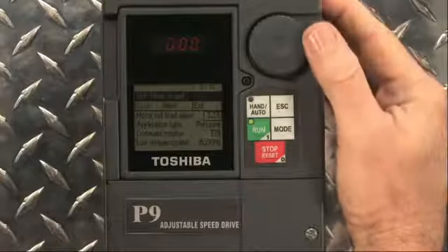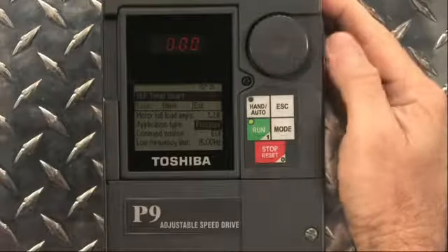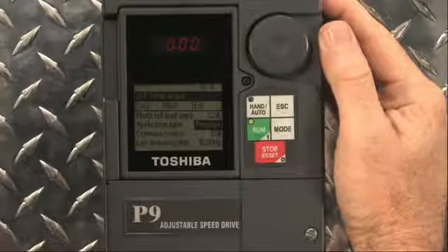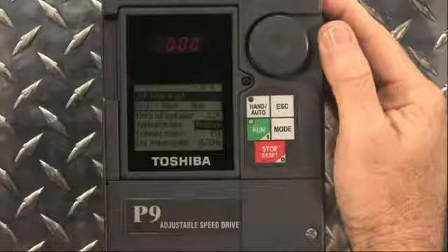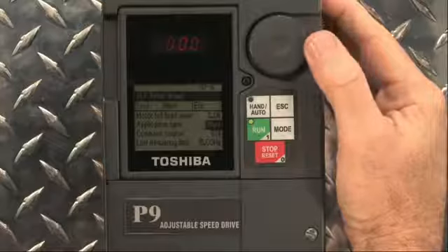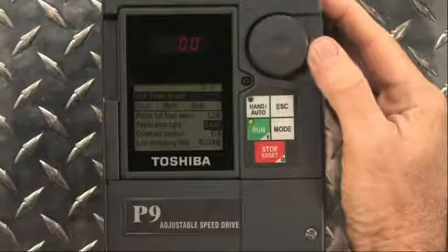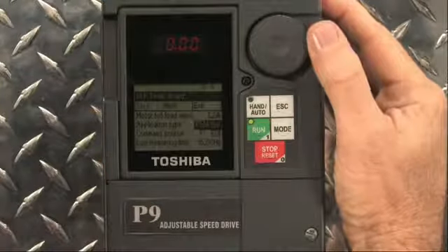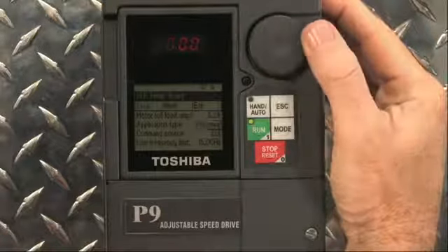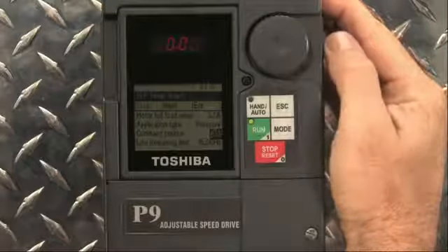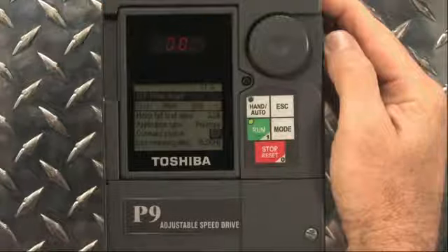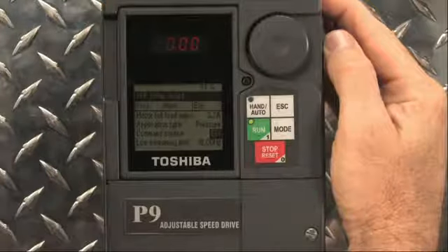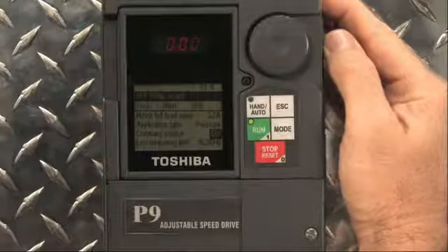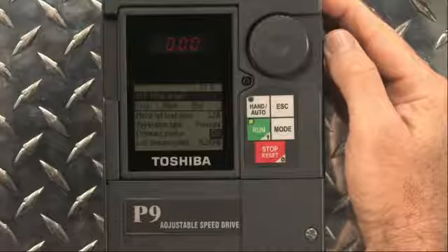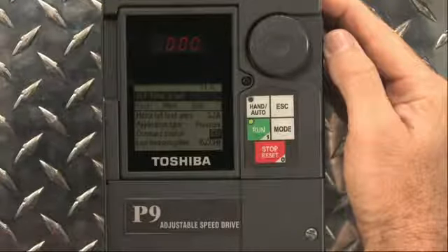The next thing we need to do is to tell the P9 what application type to control. For this demonstration, let's choose pressure. Other options include flow and level. The wizard then asks for the command source. This is where we want to control the system from. Today, we will choose EOI. EOI stands for Electronic Operator Interface, which refers to the P9 keypad. The command source can also be programmed for one of the analog inputs.